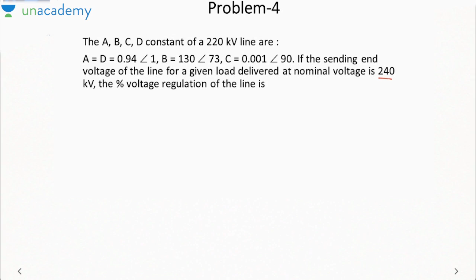Now if we put the sending end line to line voltage directly, we will get the receiving end line to line voltage, because this is a directly proportional relation. So let me directly use the line voltage, 240 by 0.94. So this comes out to be 255.32. The beauty with the voltage regulation equation is you can use either both line voltages or phase voltages. There is no hard and fast rule, because anyway the factor of root 3 will get cancelled out in the numerator as well as the denominator. So voltage regulation will be 255.32.